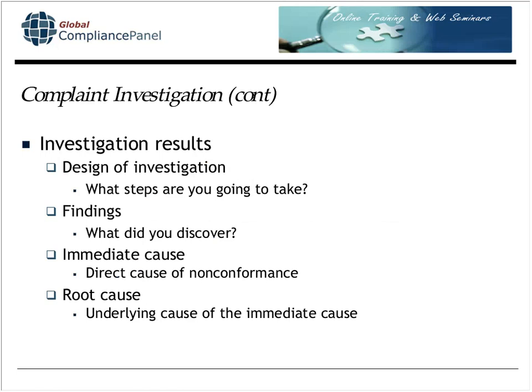After you document what you discovered, you're going to document the causes, and you're going to document the immediate cause and the root cause. Sometimes they are one and the same. Other times, not so much. If you determine during your investigation of a PC board that was returned that the resistors and capacitors were switched, that they were misassembled, that's the immediate cause. But the root cause is, why were they switched? Why did the operator make an error? Was it that they were not trained? Is it that you've discovered during investigation a lot of in-process errors made by multiple operators? Therefore, you could imply that the procedure is not that clear.